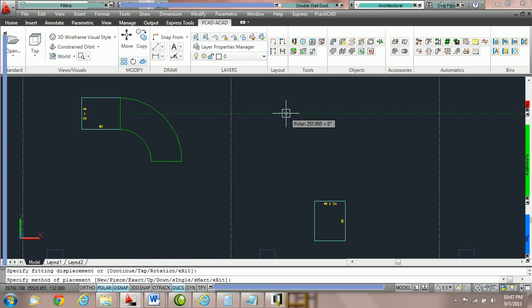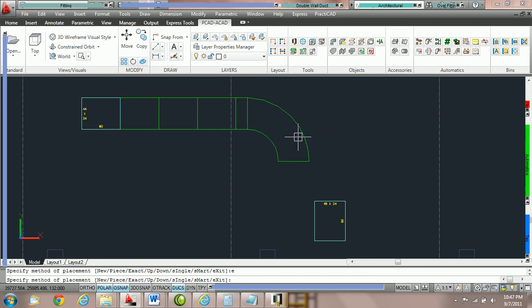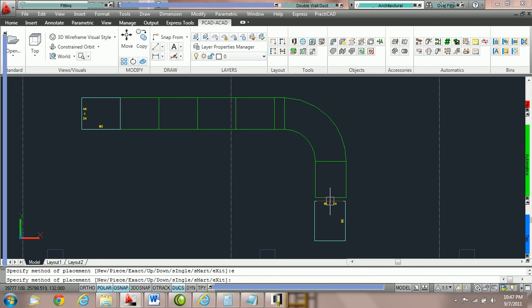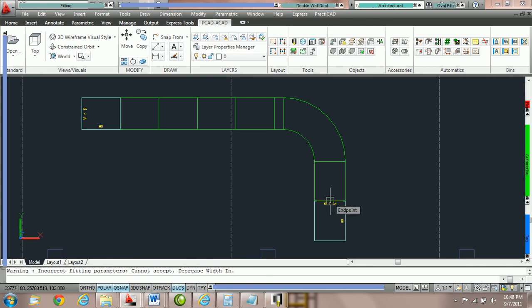Your command line should say new piece, exact up, down, single, smart and exit. What we're going to do is now hit E spacebar for exact and then pull your cursor down to the other fitting and hold it right where it's supposed to attach. Notice we haven't placed it down yet. Dependent on the distance between your two fittings you should have a little piece of variable duct right before the elbow.